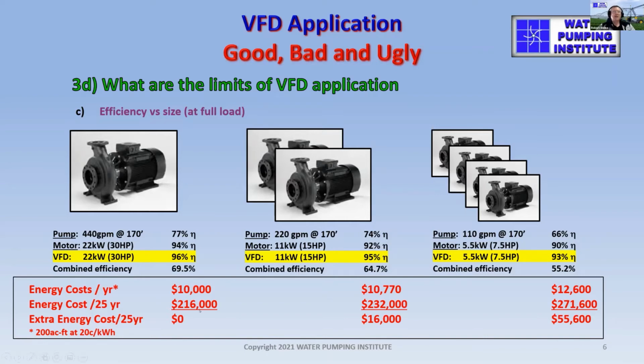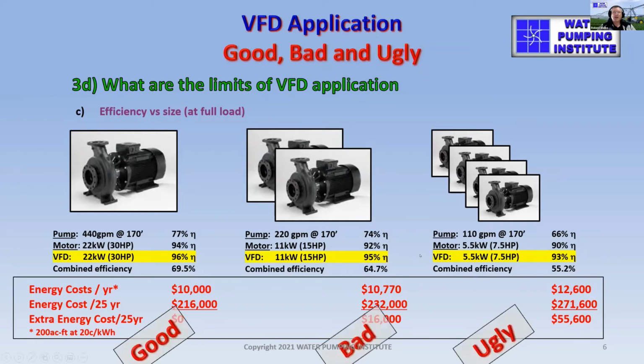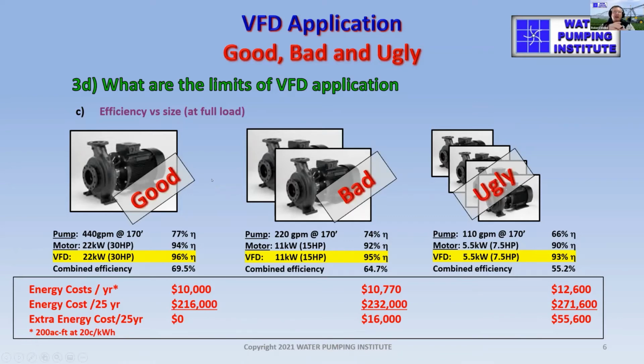So in this particular case, we find over a 25-year life, there is a $55,600 difference between the single pump and the quad pump running costs. That is enormous difference for those size pumps. So that's where the good, bad, and the ugly I've categorized as something that's good, it's something that's achievable, bad is not quite as good, and ugly is somewhere you just don't want to go.